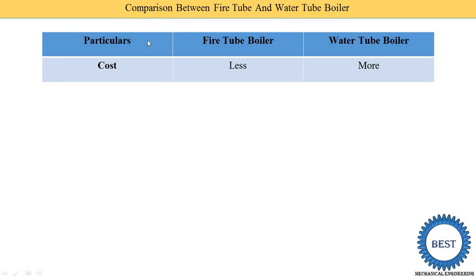The cost of the fire tube boiler is less and water tube boiler is higher. The pressure is higher in water tube boiler, so when pressure is higher we require a larger thickness of the pipe or the shell, and larger thickness increases the cost of the water tube boiler. In a fire tube boiler the pressure is near to 25 bar, so compared to the water tube boiler, fire tubes require less thickness of the tube and shell, meaning less material cost and overall cost of the fire tube boiler is reduced.